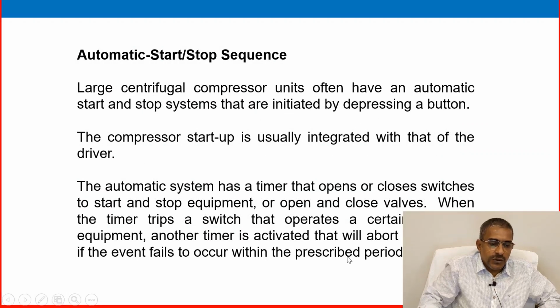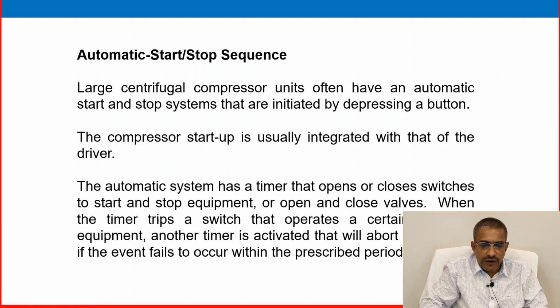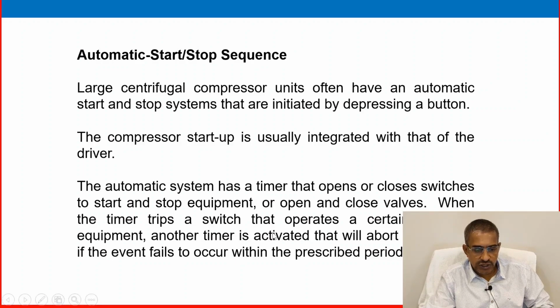Automatic start stop sequence. Large centrifugal compressor units often have an automatic start stop sequence that is initiated by depressing a button. The compressor startup is usually integrated with that of the driver. The automatic system has a timer that opens and closes switches to start and stop equipment and open and close valves. When the timer trips a switch that operates a certain piece of equipment, another timer is activated that will abort the startup if the event fails to occur within the prescribed period of time.